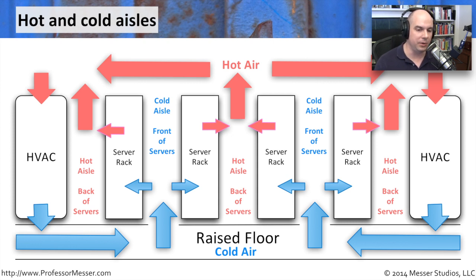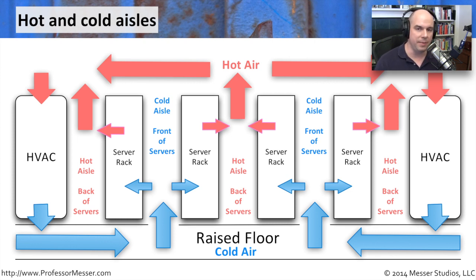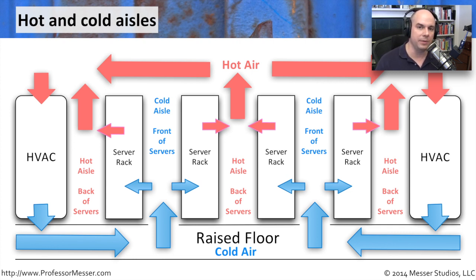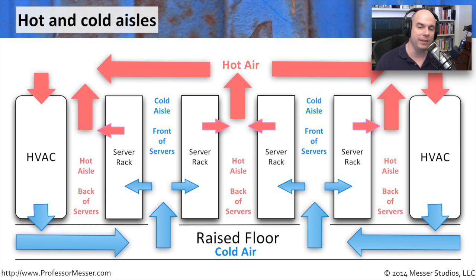So all of your computers — if we were to go down this aisle and look to the left or right, we would see the front or the back of servers facing us. Underneath these data centers are raised floors, and we have cold air going between all these raised floor systems, blowing up into openings that we have in the floor — blowing up into a set of racks where the front of our servers are.